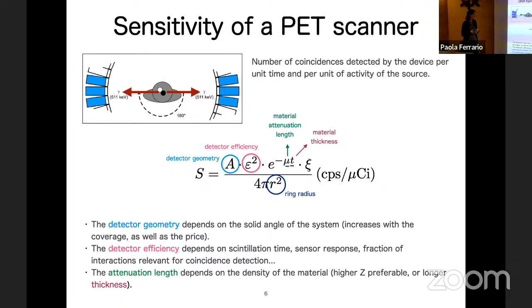And then the kind of material that you use, ideally you want to stop as many gammas as possible. So the material should be very dense, high Z number. And if you have not that dense a material, then you have to compensate with a longer thickness in order to stop as many gammas as possible. On top of that, there is another characteristic present in some of the scanners, which is the ability of detecting the time of these 2 gammas when they arrive at your detectors.